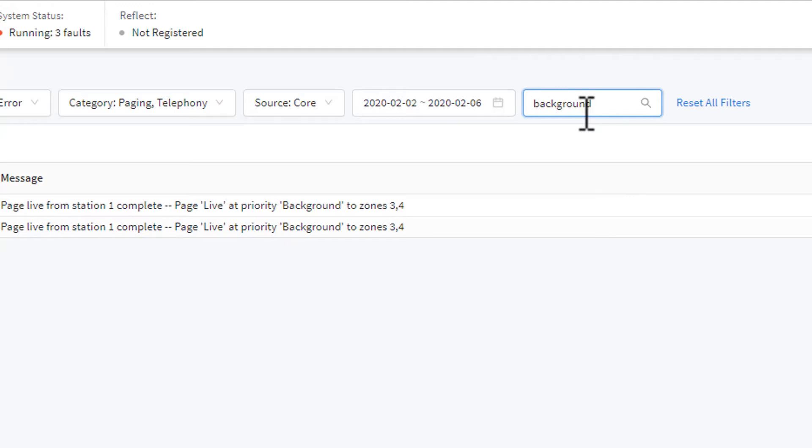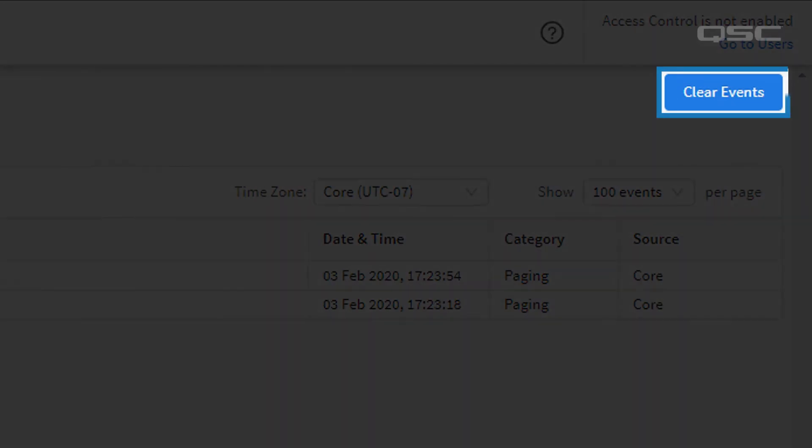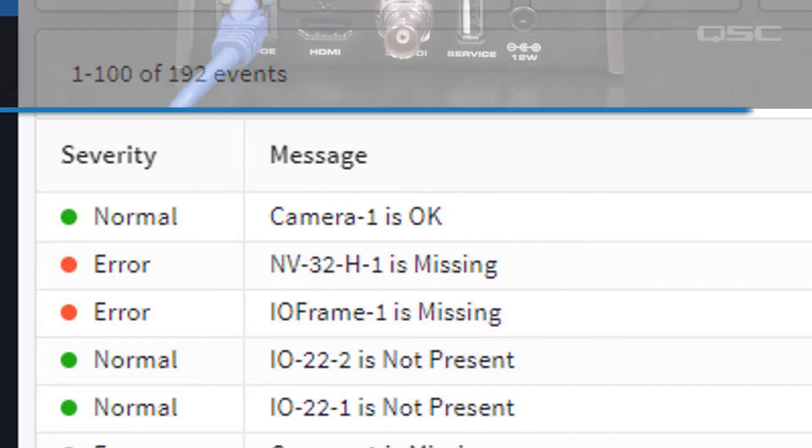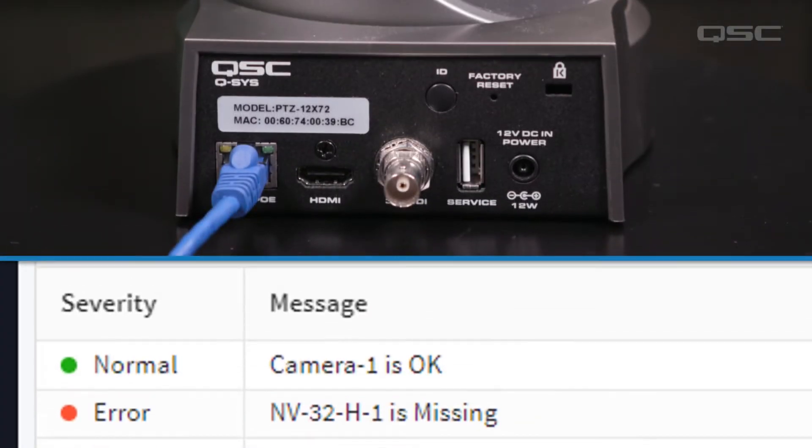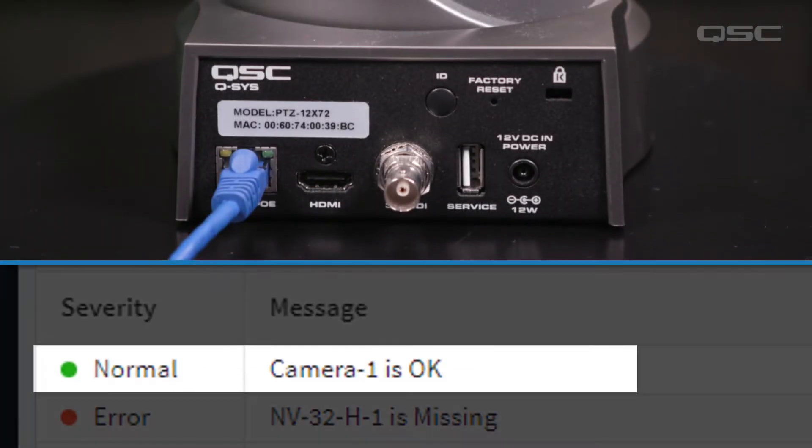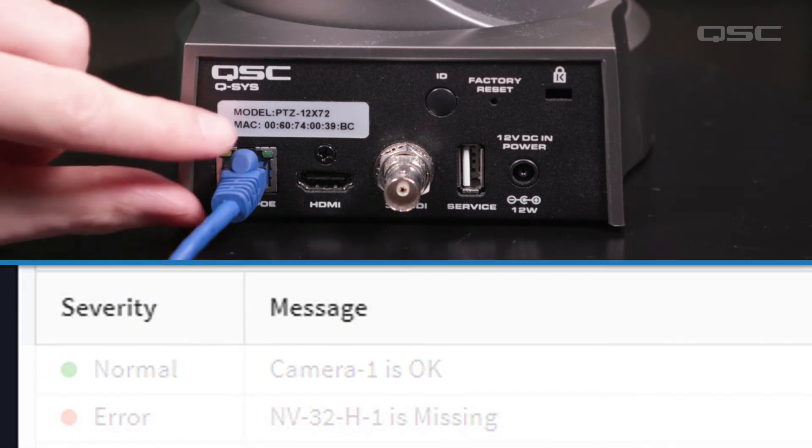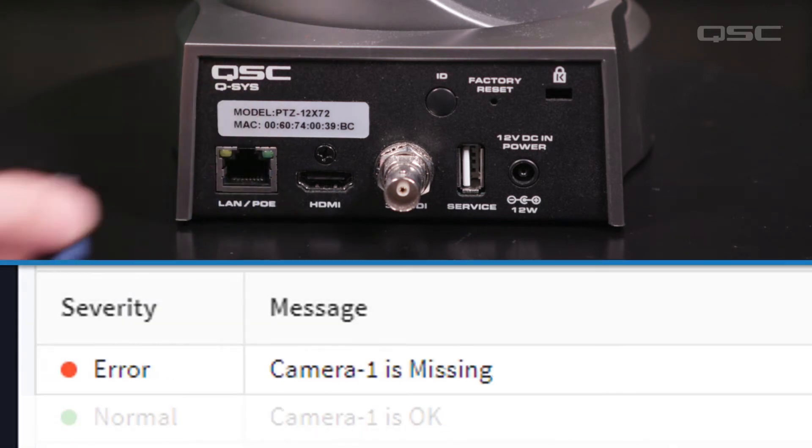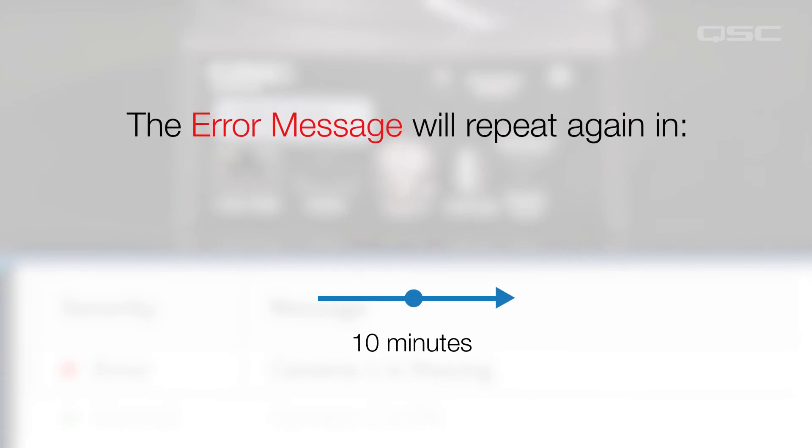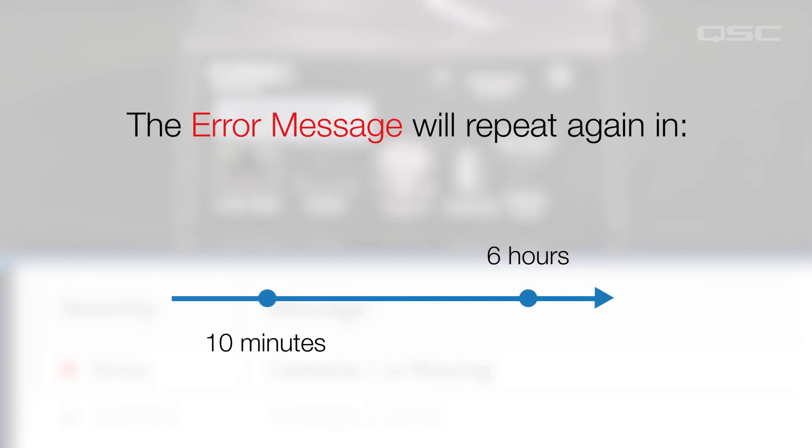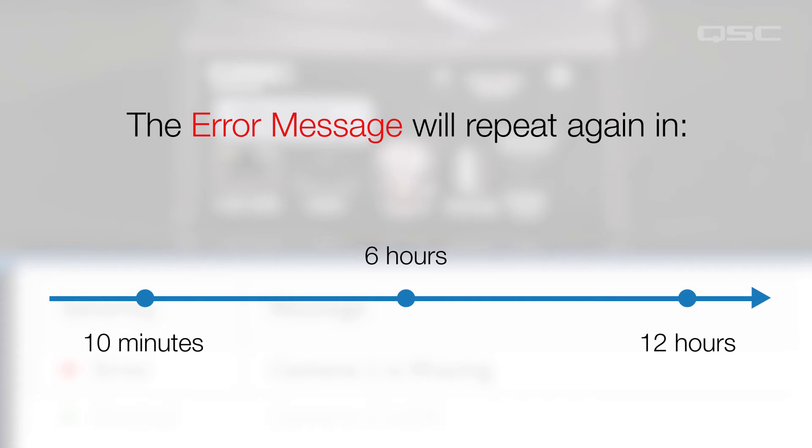Or, if you want to clear out your log, simply press the Clear Log button. Certain events in a log will repeat. For instance, if a device's status drops from OK, then an error message will log upon the first problem, and then repeat again in 10 minutes, then 6 hours, and then every 12 hours thereafter until the problem is corrected. The log will also specify how long the problem has persisted.